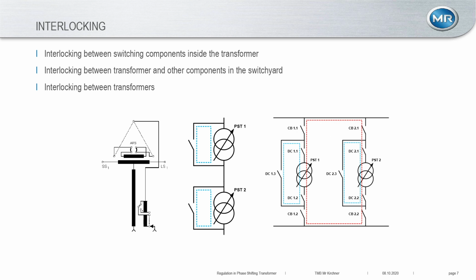And in this, and only in this position, you are allowed to operate the advanced retard switch. So this interlocking will be realized by MR. So this is not the problem because we are focusing on that. So if we know the design, if we know you use advanced retard switch, we are going to realize this interlocking.